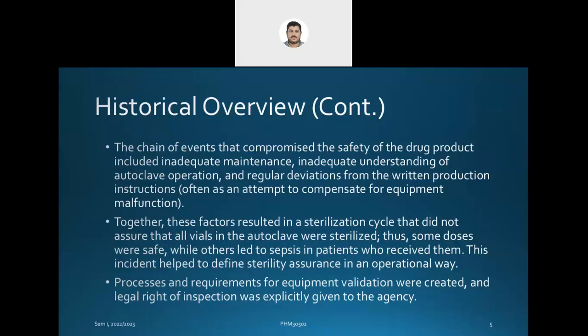At this time they used to have regular deviations from the written production instructions, done in order to compensate for equipment malfunction. So there was a problem with the equipment. They made some changes that they did not document in the procedure for operating the autoclave, and they thought that by doing this they would overcome the performance problems of the apparatus. But actually they did not overcome them, and there was a problem of inefficient sterilization. Okay, so some of the product was not sterilized and caused the deaths of patients. These factors resulted in a sterilization cycle that didn't ensure that all vials in the autoclave were sterilized.